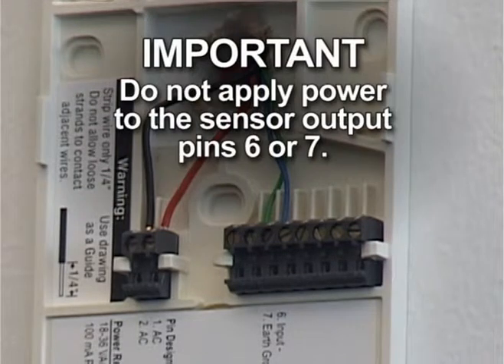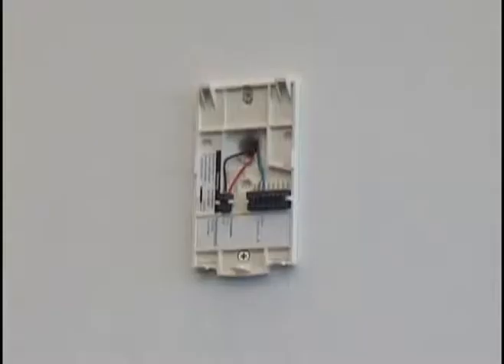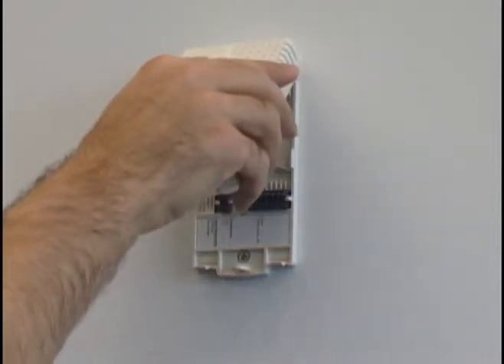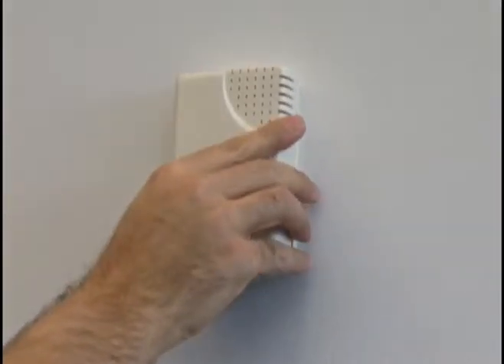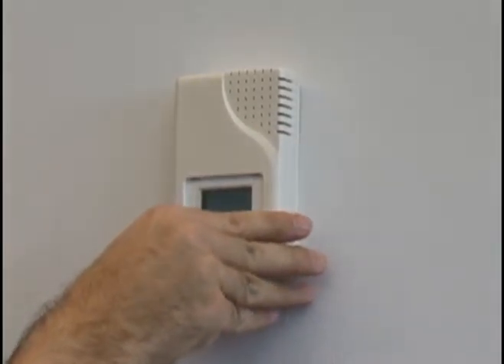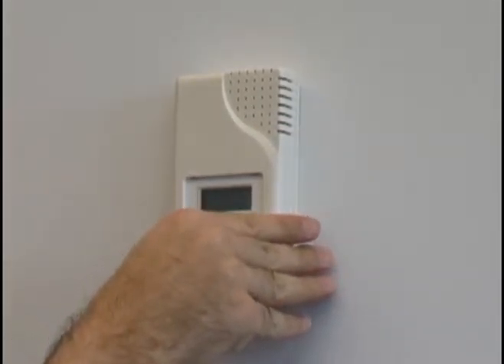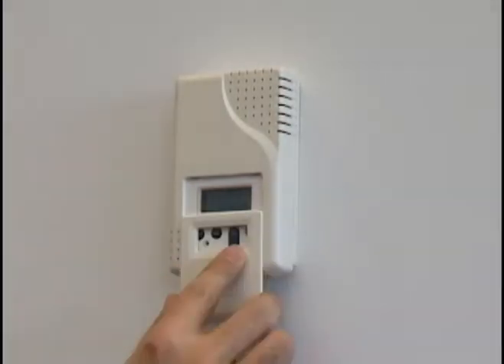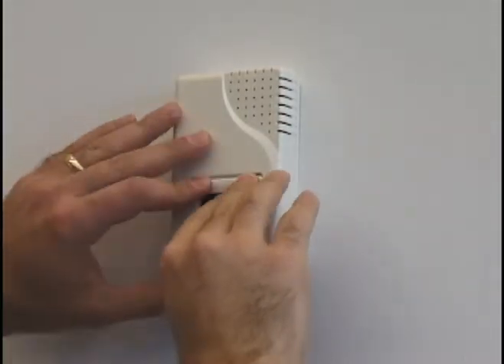It is very important to ensure that the 24-volt power wires are never applied to output pins 6 or 7, as this may damage the sensor and voids the sensor warranty. After wiring the VaporStat backplate, snap the sensor into place by aligning the slots in the top of the sensor to the backplate and pivoting the sensor downward until it snaps into place. Then insert the locking cover and secure it with the included locking screw at the base of the sensor.